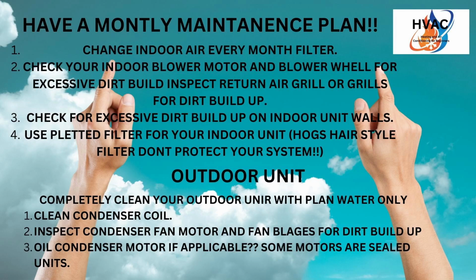A word of caution: those fins are susceptible to bending, so do not use a pressure sprayer on it. Get one you can control the pressure with. You want mild pressure, not heavy pressure, because if you go side to side across that fin you'll bend them, which reduces your airflow. If that happens, they make a tool at Home Depot called a fin comb that you can run down there to fix it, or you can take a small screwdriver and bend those back. It's going to happen - it's not totally avoidable, but you can fix that problem.